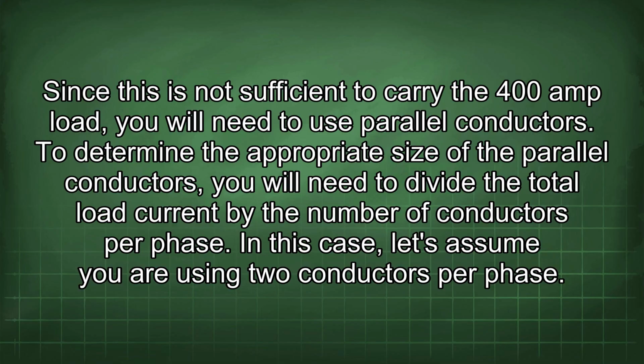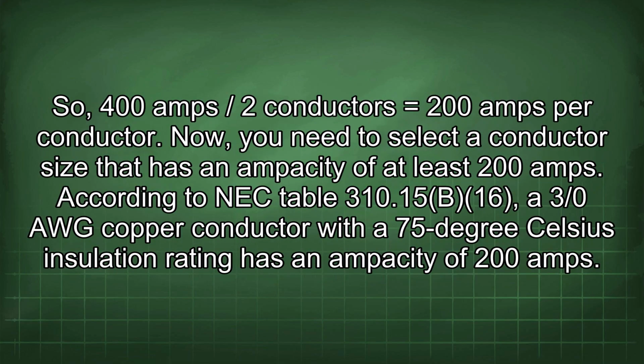To determine the appropriate size of the parallel conductors, you will need to divide the total load current by the number of conductors per phase. In this case, let's assume you are using 2 conductors per phase. So, 400 amps / 2 conductors equals 200 amps per conductor. Now, you need to select a conductor size that has an ampacity of at least 200 amps.